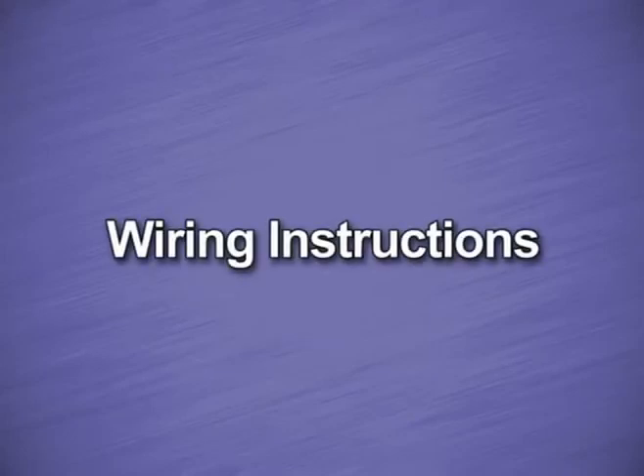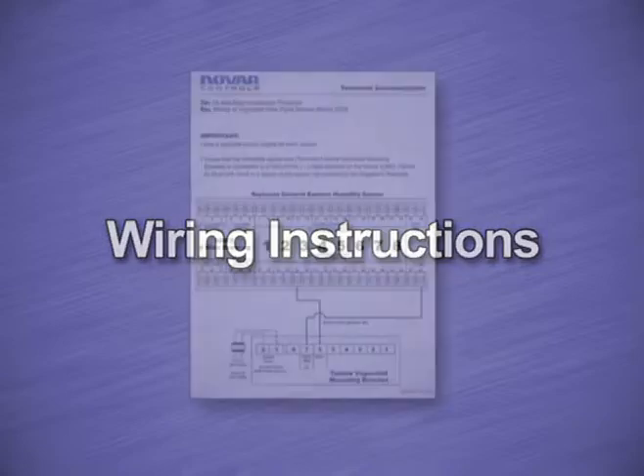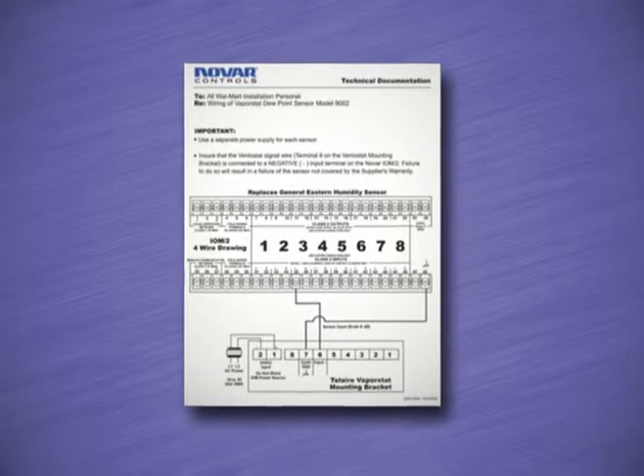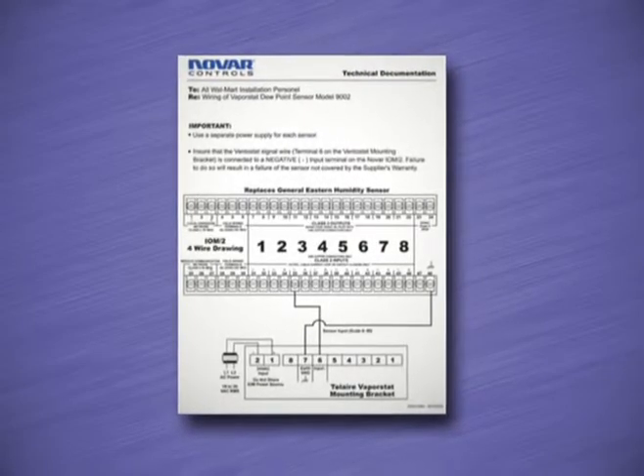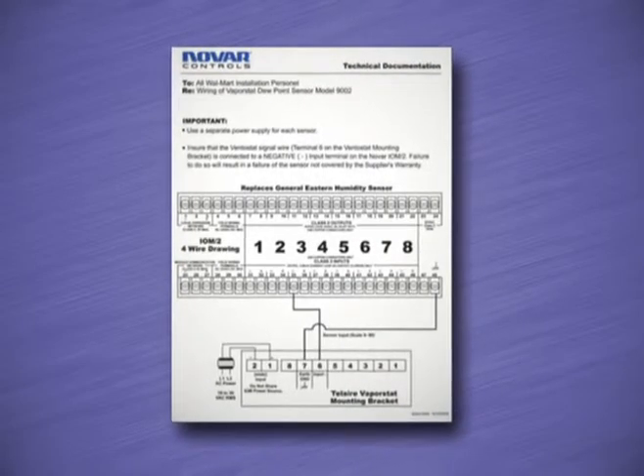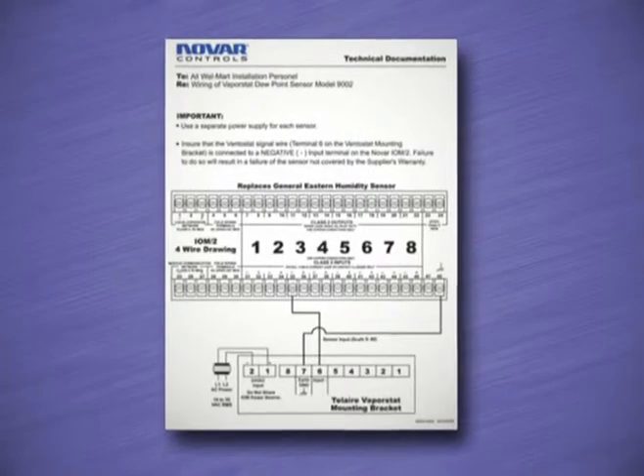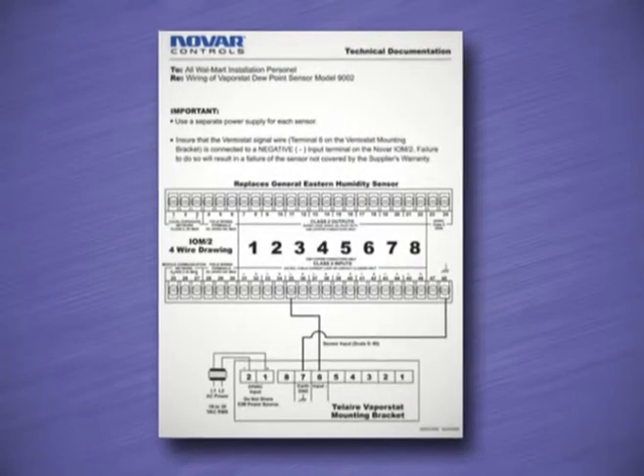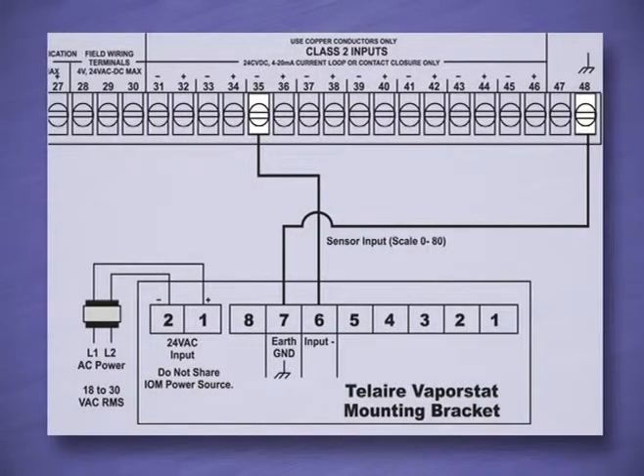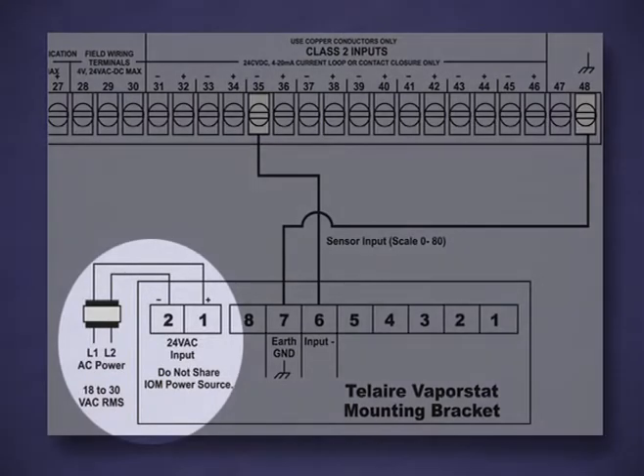First, we will review the wiring and installation requirements for connecting a VaporStat to a Novar Input-Output Module, or IOM. Wiring the VaporStat to the IOM is a straightforward 4-wire installation. Please consult the custom wiring diagram that comes with each VaporStat sensor. In the installation, 24 volts AC is supplied from a dedicated transformer to pins 1 and 2 on the 9002.